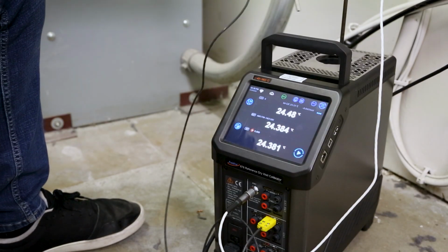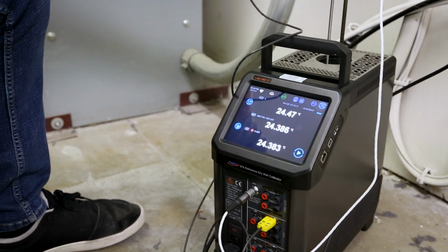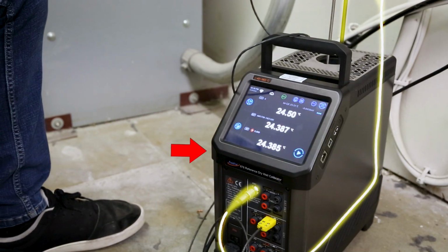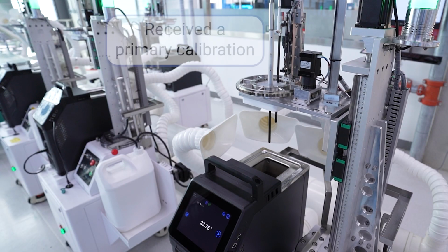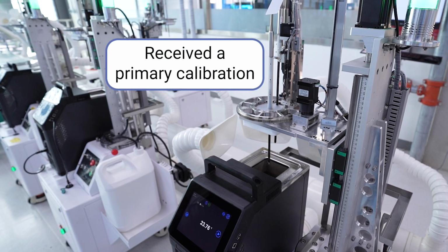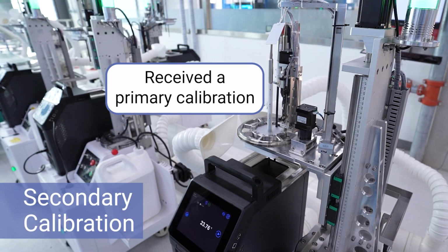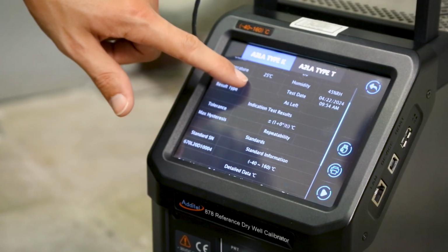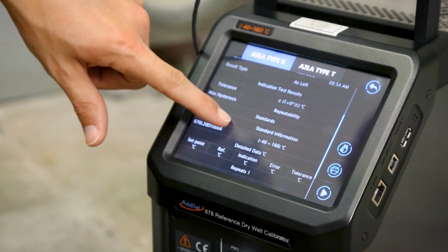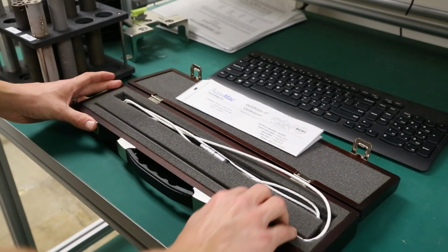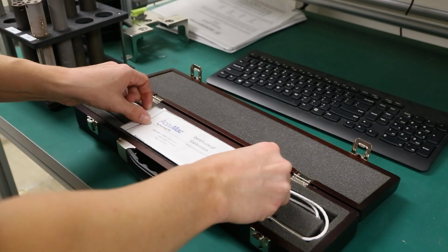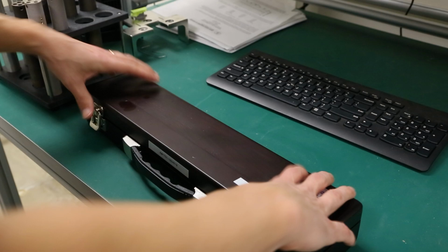Calibrations for lower accuracy temperature devices are often performed in the field, using a portable reference and temperature source. Using a device that received a primary calibration as a reference is known as a secondary calibration. After comparing the readings of the UUT and the reference across multiple temperature set points, the UUT will either pass calibration and remain in service, or fail and need to be adjusted or replaced.